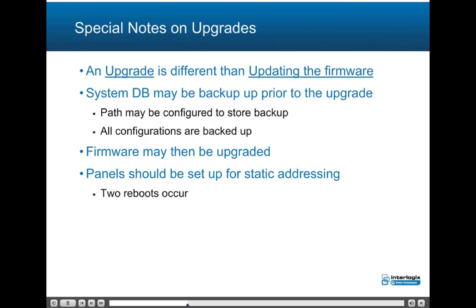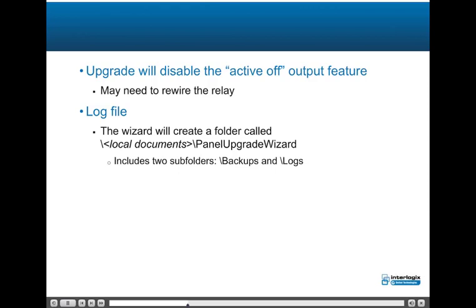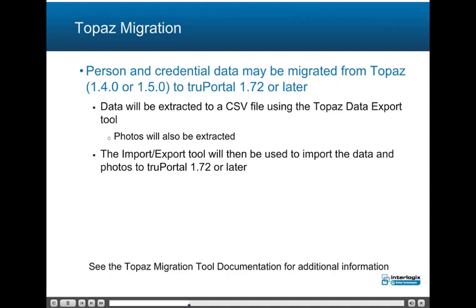For existing truPortal 1.0 and GoEntry 3.0 customers, the upgrade will disable the Active Off Output feature, which may require rewiring certain relays. The wizard will create a folder called \local documents\panel upgrade wizard, which includes two subfolders: \backups and \logs.